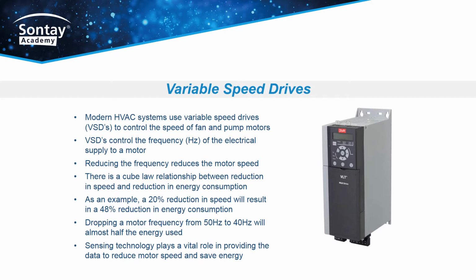In-depth knowledge of the workings of a VSD is beyond the scope of this presentation. However, the important factor is the non-linear relationship between motor speed and energy consumption, which follows a cube law relationship, meaning that any percentage reduction in speed will result in a much larger reduction in energy consumption. In the example above, we are reducing the speed by 20% of its previous value, i.e. the new speed is 80% or 0.8 of what it was. Using the cube law, we can calculate that the corresponding power reduction will be 0.8 by 0.8 by 0.8, which equals 0.512 or 51.2% of its previous value.